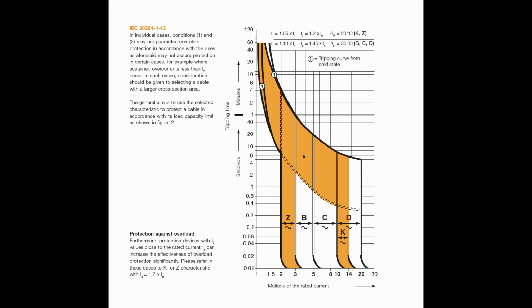And the difference between the two lines, so say on the B between 3 and 5, is just that it will trip somewhere between the current there. The actual time it takes to trip is going to be the same, it just depends on the individual device. Now the top part of this graph, which is the curved section, that's actually the thermal part of the circuit breaker, and that's actually the same for all of the types, hence the lettering doesn't actually extend up that far.